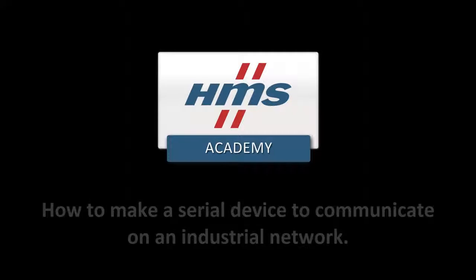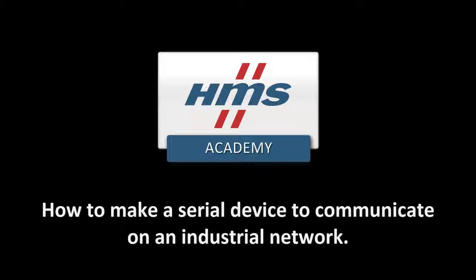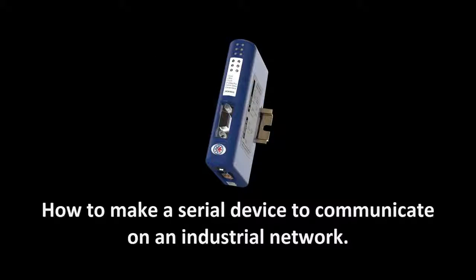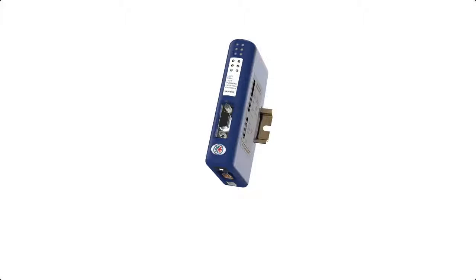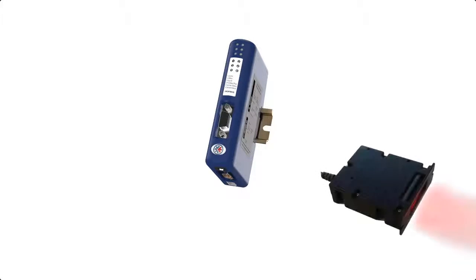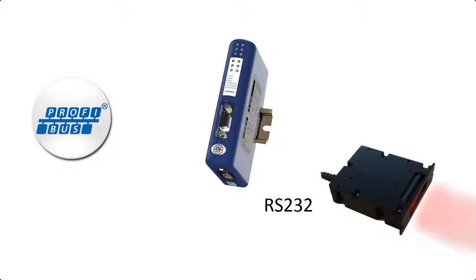In this demo, we will show how to make a serial device communicate on an industrial network. To do this, we will use the Anybus communicator as a gateway. In my scenario, we have a barcode scanner using RS232, which I want to access from a PROFIBUS network. I've connected the barcode scanner to the bottom interface of the Anybus communicator and the PROFIBUS cable to the front.